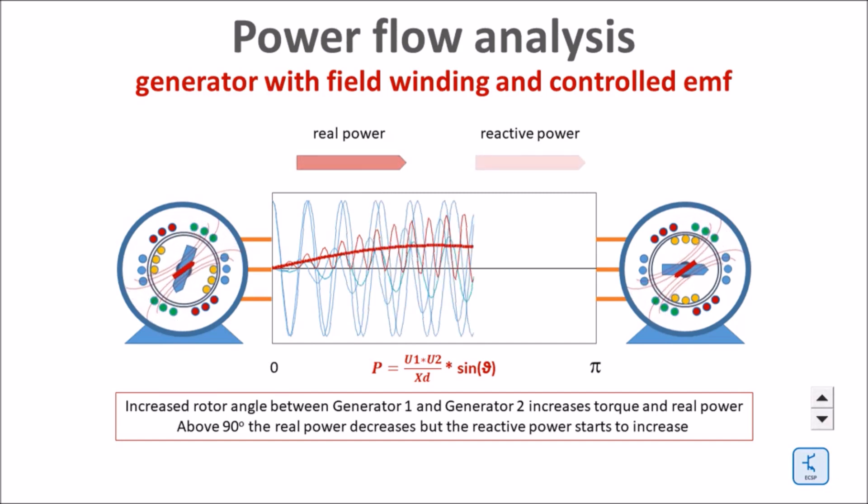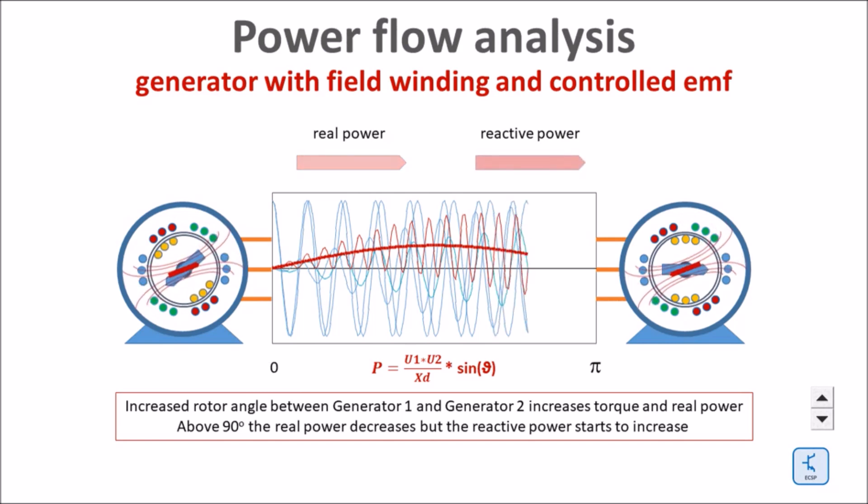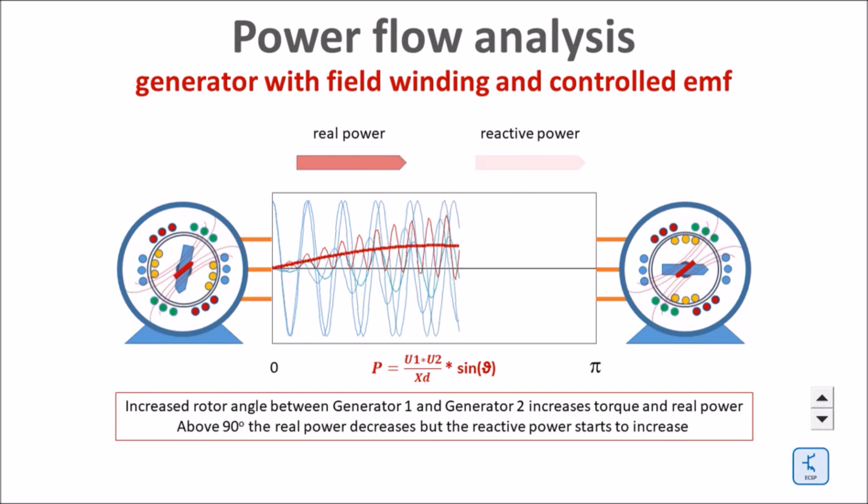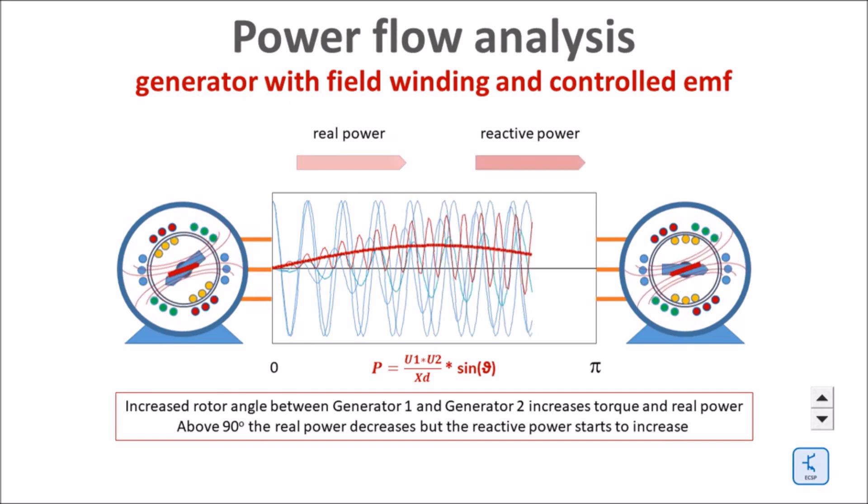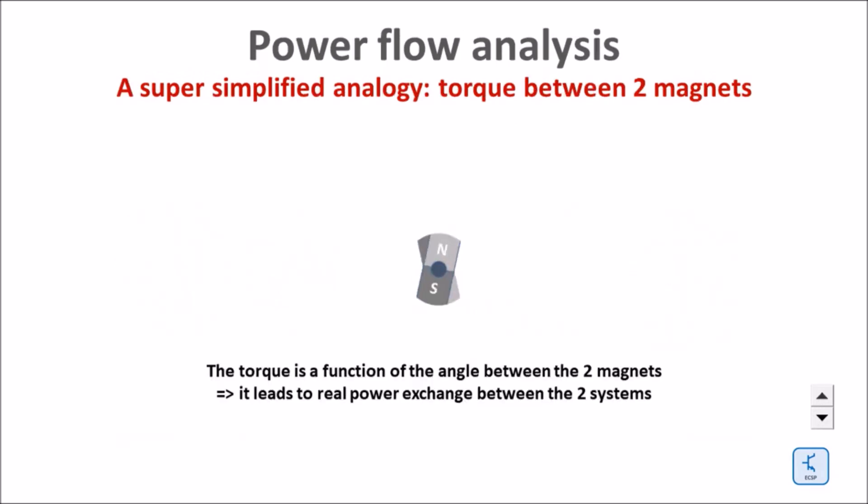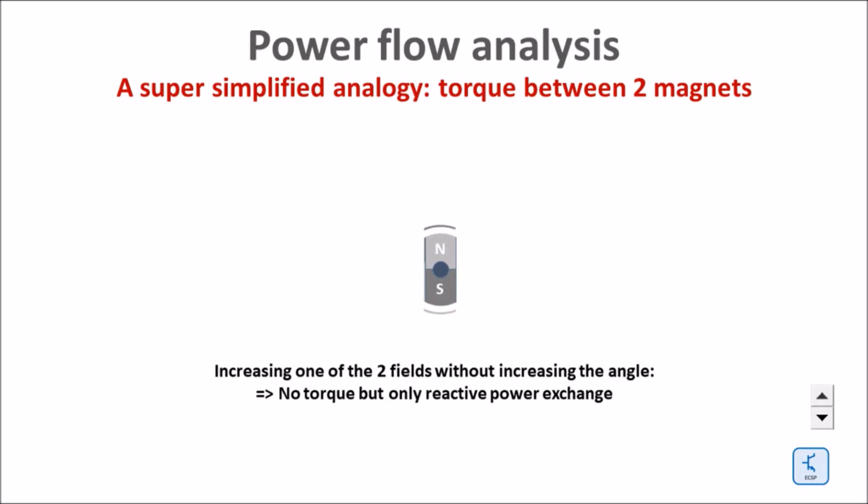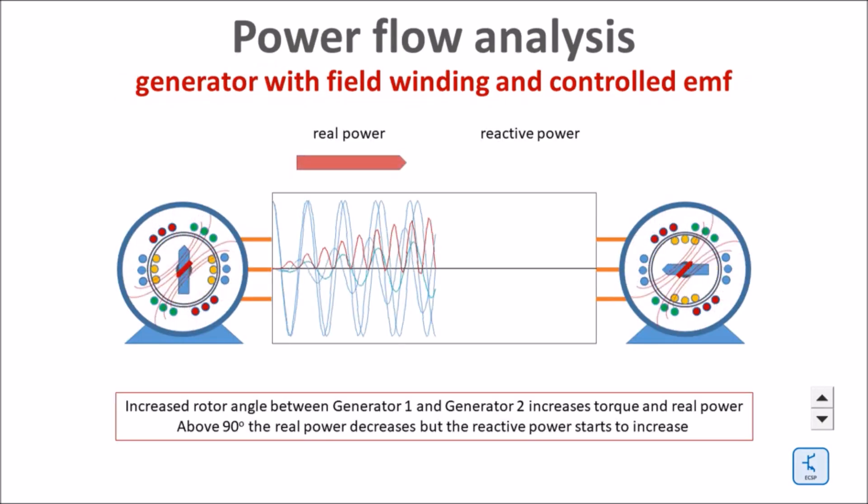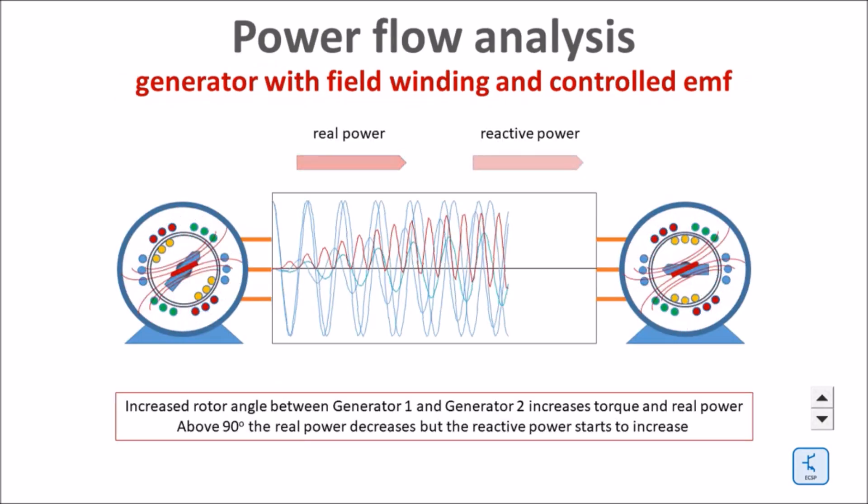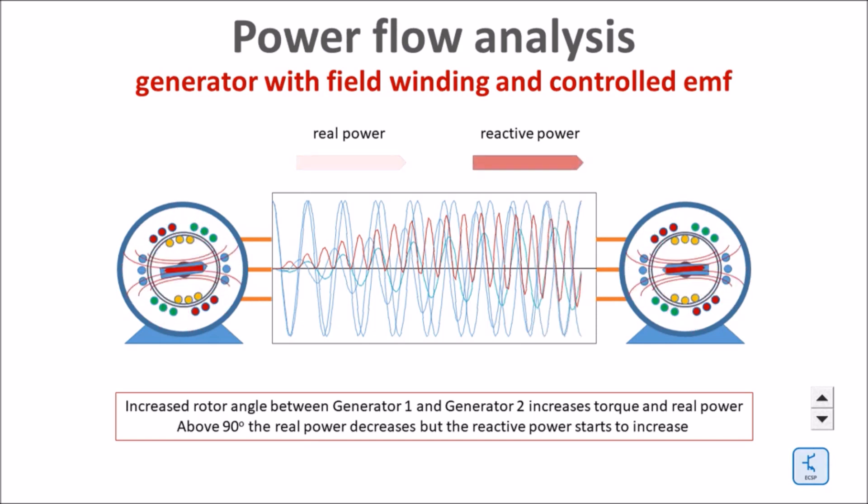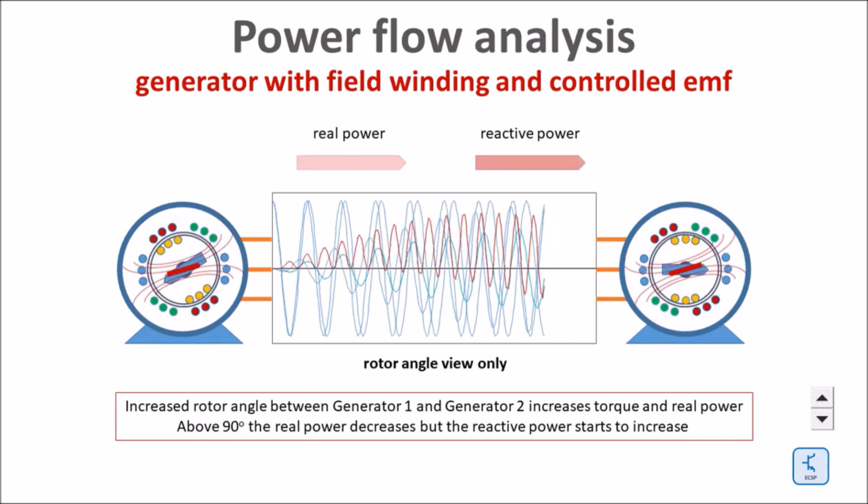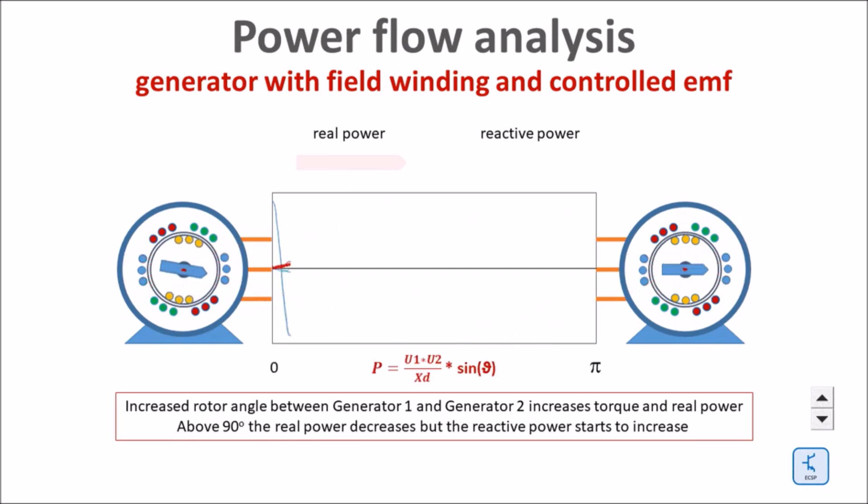At the end both components, the real power and the reactive power, are affected by the rotor angle. This was a tough one right? As a mnemonic keep this one: real power when there is a torque between the two magnets. If you just increase one of the two magnets without increasing an angle you just get reactive power. Short summary: in order to produce real power you need a rotor angle. In order to get the rotor angle you need a torque and the torque is established by means of a turbine.